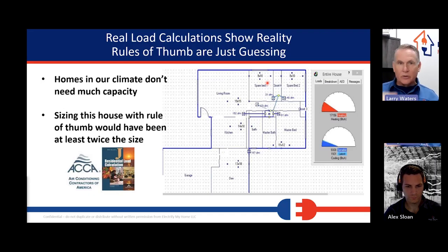We came in and actually did the load calculation. Now, what this customer had done before we came out to the house is they installed all new windows. There was a shade structure back here. And we insulated the attic space once this was all installed. We, as in the company I worked at when this was done. This was a number of years ago. So we did a load calculation on this house. The only assumption that we built into this load calculation, other than what was really here, was the attic space that we were going to insulate, and we calculated these ducts being inside the building envelope.